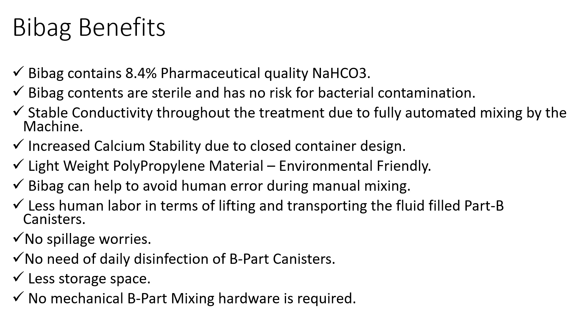Open B-Part solution containers usually allow the dissipation of carbon dioxide gas from the bicarbonate solution, which causes a reduction in calcium stability in the dialysate due to precipitation. Since Bi-Bag is a closed airtight container, it will not allow carbon dioxide gas to escape, and by this way the calcium stability in the solution will be maintained. Bi-Bag is made up of a lightweight polymer called polypropylene and hence it is eco-friendly.